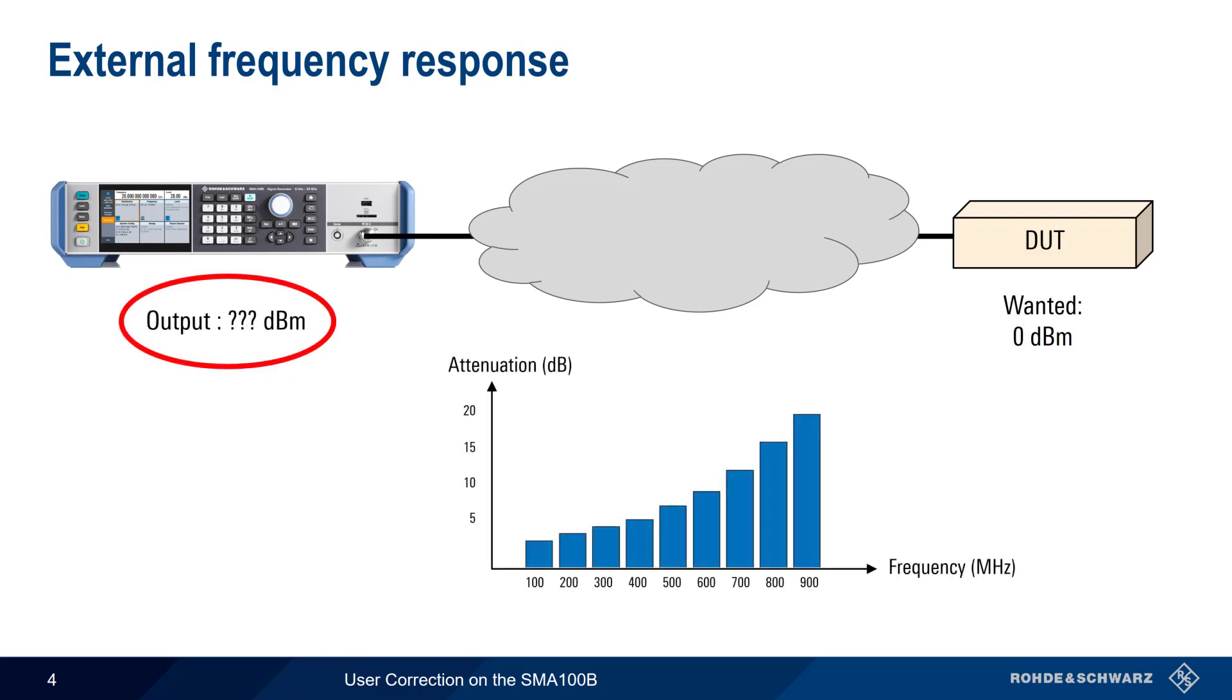What power level do we set on our generator for a given frequency? We could try to calculate and set this manually, but the more accurate and efficient way of compensating for this external frequency response is using something called user correction.